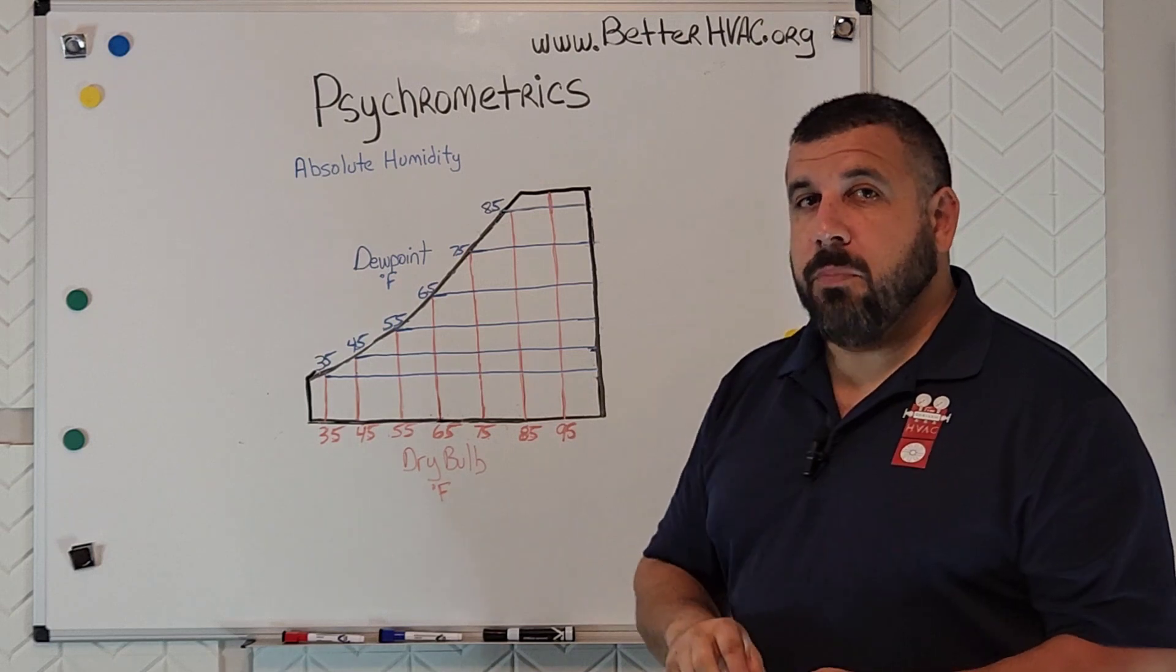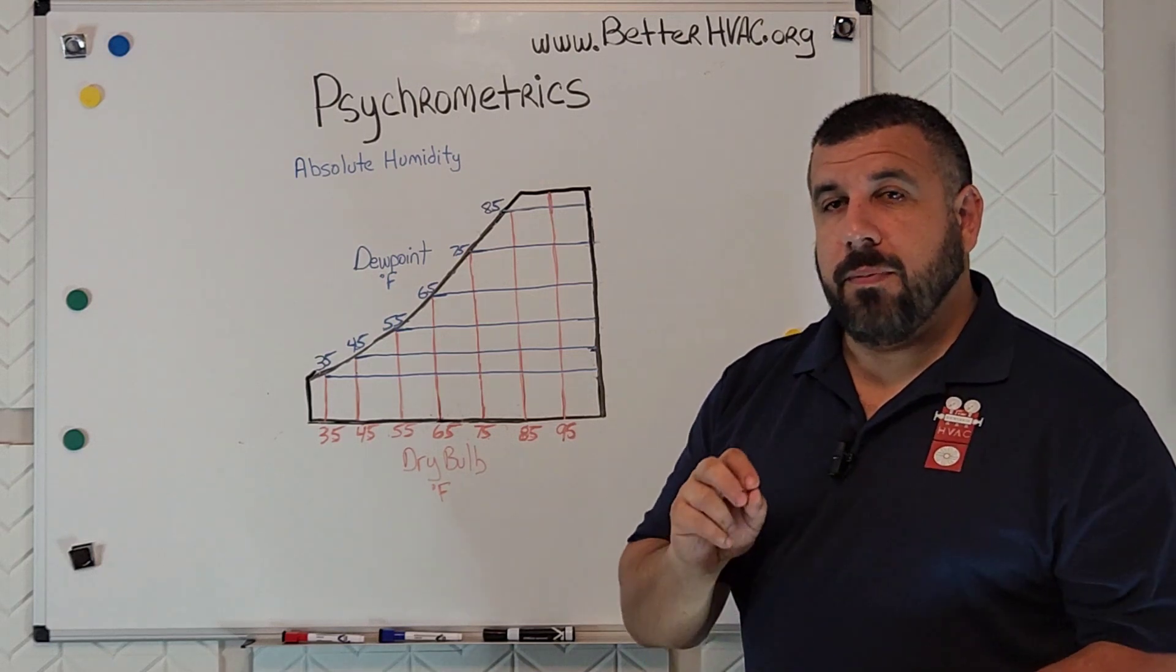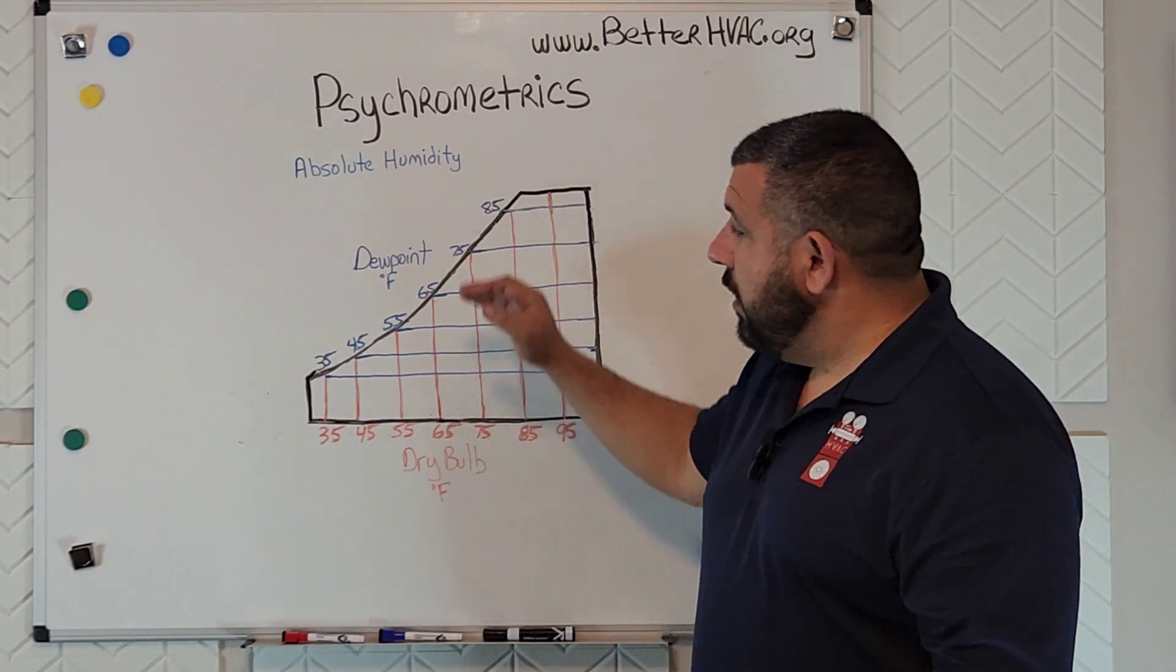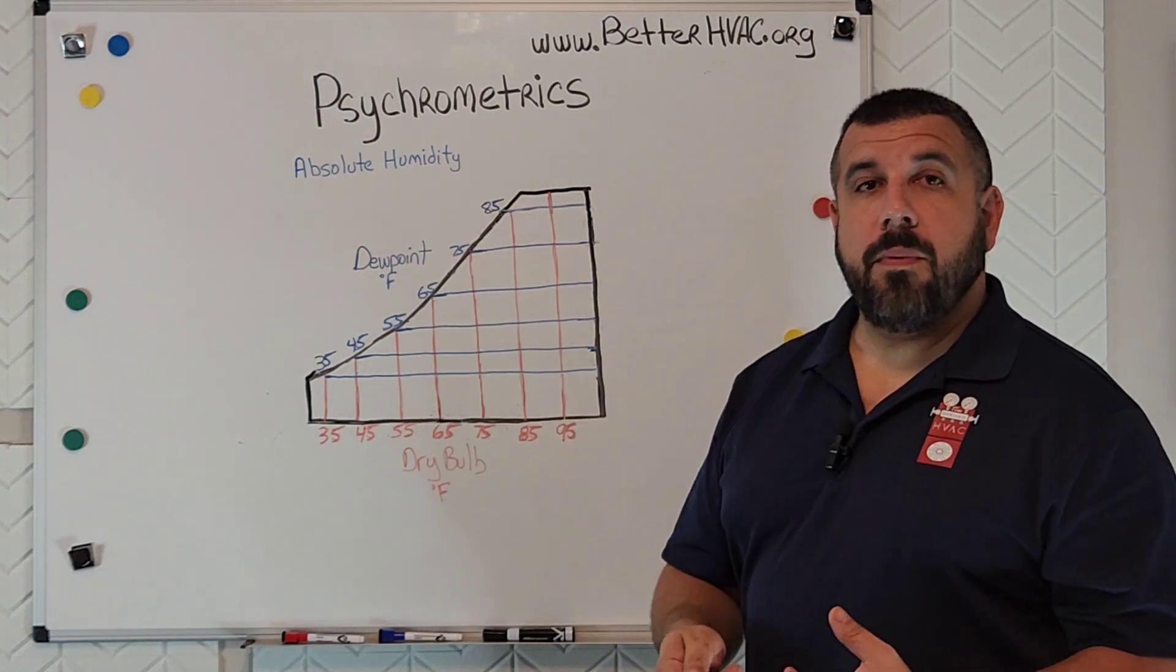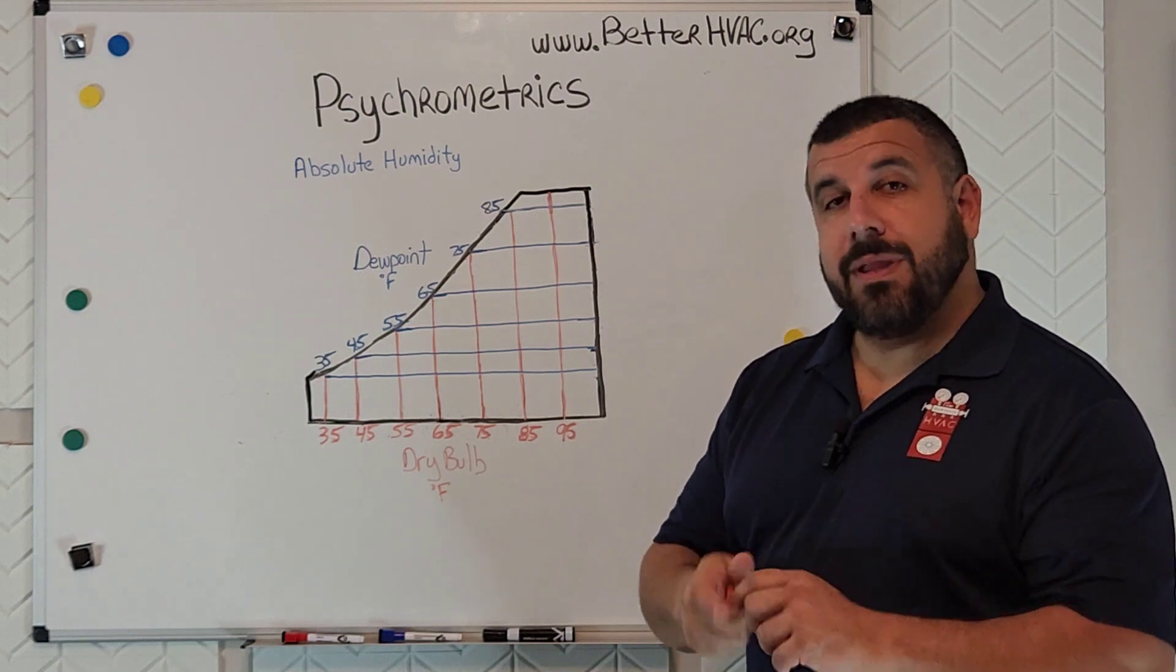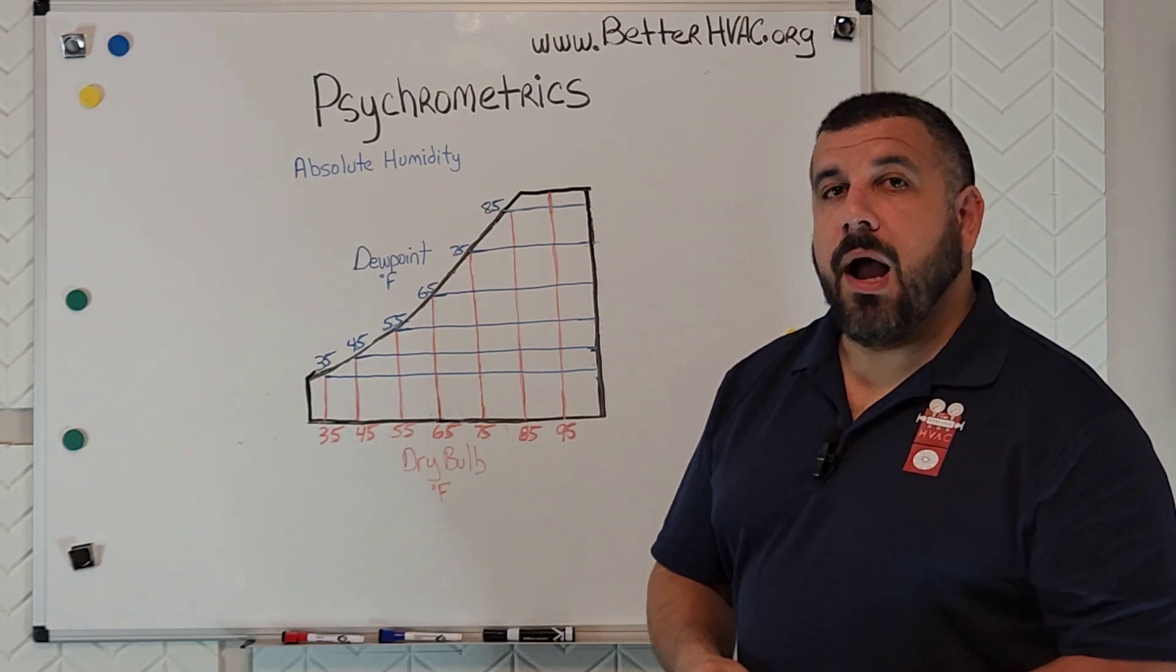So we're going to plot our very first point on the psychrometric chart, because anytime you know two properties of the air, such as dry bulb temperature and dew point or another property, then where those two lines intersect, that is your operating point.